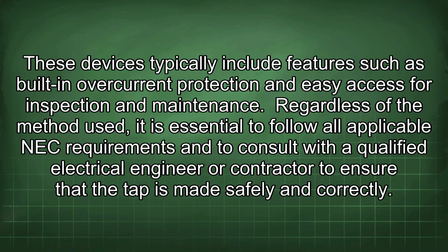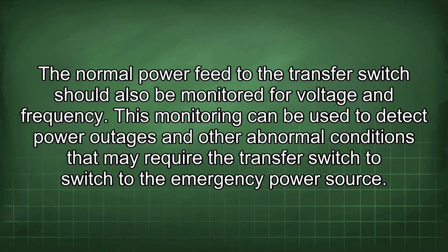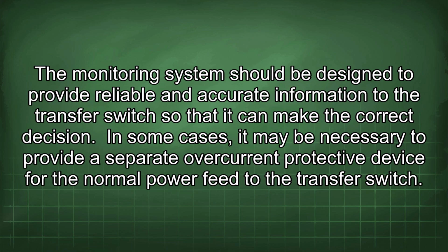Regardless of the method used, it is essential to follow all applicable NEC requirements and to consult with a qualified electrical engineer or contractor to ensure that the tap is made safely and correctly. The normal power feed to the transfer switch should also be monitored for voltage and frequency. This monitoring can be used to detect power outages and other abnormal conditions that may require the transfer switch to switch to the emergency power source. A monitoring system should be designed to provide reliable and accurate information to the transfer switch so that it can make the correct decision.